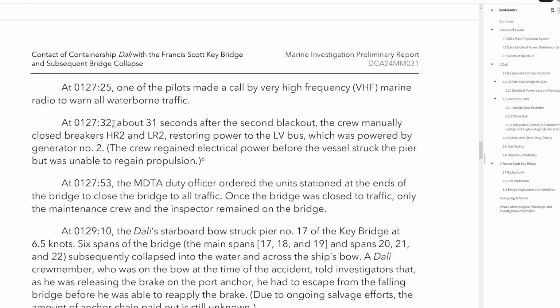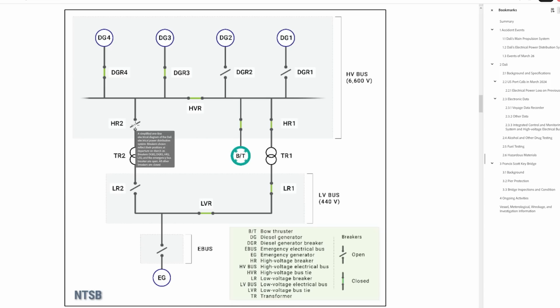At 1:27:32, 31 seconds after the second blackout, the crew manually closed breakers HR2 and LR2, restoring power to the low voltage bus, powered by generator 2. So they had regained electrical power before the vessel struck the pier, but they were still unable to regain propulsion. Closing HR2 and LR2 let power flow through this path all the way down to the low voltage bus. You can see it's a nice redundant design.